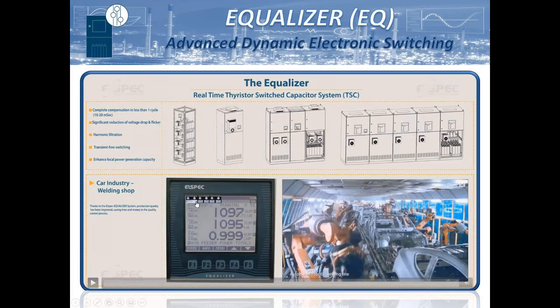So in a balanced system, we treat all three legs equally in the sense of compensation. So we base the compensation on the average of the three legs, whereas in an unbalanced system, we take each leg independently. This is most commonly used in welding type applications, where you have vast differences between the phases on demands. So in seeing that, you'll notice that these three bars in those systems can actually operate independently. So just giving you a little bit of background on what you're looking at, but we'll go ahead and try to play this quickly and see how this goes.